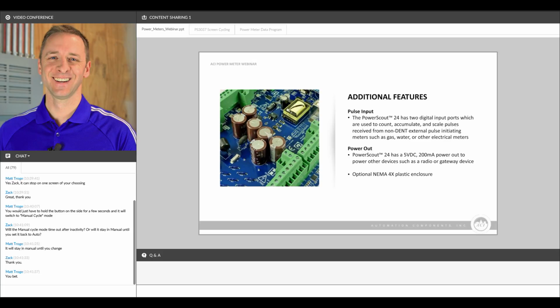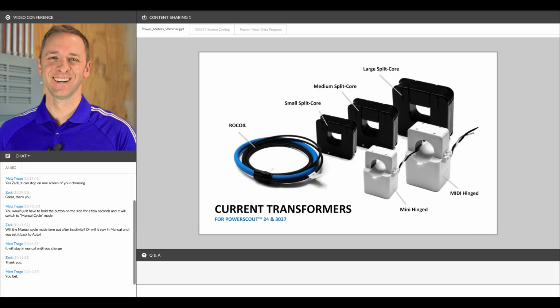And it also has an external power supply built in that can handle 5 volts DC up to 200 milliamps. So this device can power any external devices such as data loggers or radios or gateways. And it is available in an optional NEMA 4X enclosure that can be a simple standalone enclosure for your panel mounts. Let's get into the accompanying CTs.